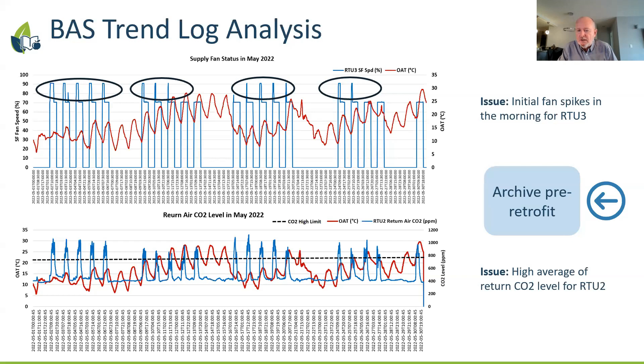The scheduling is pretty consistent, and you can see the fans aren't coming on during unoccupied periods, so that's good. Below, we see CO2 levels as a really good indicator of how much outside air is coming into the schools. The recommendation is that we need to be archiving building automation trends and profiles before and after these projects, so you can compare and see what changed.